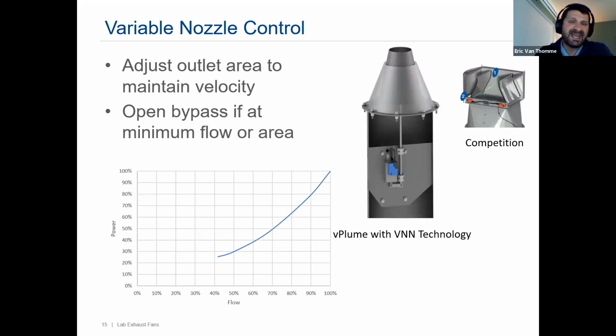One of the most unique features we came out with about 12 to 16 months ago or so is on our high velocity fan, our V-Plume style fan. We've created something that allows the user to adjust the outlet area of the fan as they reduce the fan speed. So again, more for energy control, users may want to reduce the fan speed a little bit from an energy control standpoint. And we allow you to adjust the outlet area so you can maintain a consistent velocity. We call this our VNN technology.